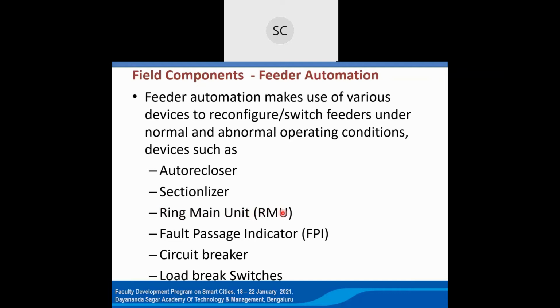Another point is that ring main units are generally seen where essential services are located, like hospitals, police departments, the secretariat, or the assembly. These are essential, strategic locations, even though they have backup through diesel generators or other alternatives. The RMU helps a lot in abnormal situations. If any one feeder or substation faults, we can extend power to the essential services. Generally these ring main units are where underground cables are there, so you can see a lot of RMUs on the road sides.